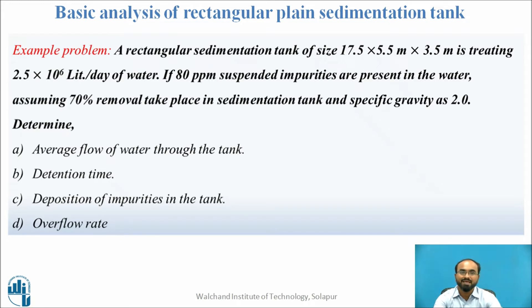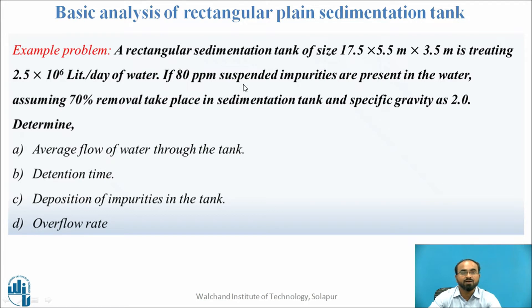All these terminologies can be explained with an example problem. A rectangular sedimentation tank of size 17.5 m (length) × 5.5 m (breadth) × 3.5 m (height) is treating 2.5 × 10⁶ liters per day of water. 80 ppm suspended impurities are present, 70% removal is assumed, and the specific gravity is 2.0. We need to determine: average flow of water, detention time, deposition of impurities, and overflow rate.